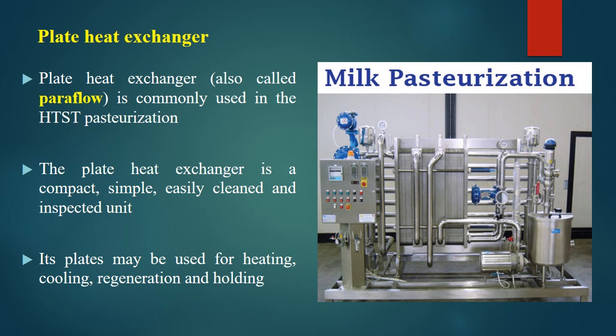Initially milk gets heated by the already pasteurized milk going out, that is the regeneration section, and then cooling is done by changing the media, in a separate section, and then the holding section where the final heating happens by holding it for 15 seconds at a specific temperature like 72 degrees Celsius. Some of these things I am going to discuss next.